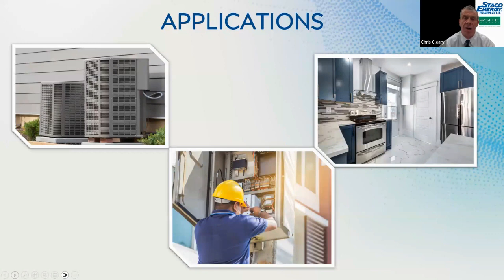We also have customers who are involved with UL 508 panels, where they're going to have to test the various different circuits that are within there. Is there some type of a circuit breaker? What does the circuit breaker do? You subject it to, say, 15 volts and 3,000 amps, and see what the circuit breaker would do in terms of its performance, so that you can be confident when it's moved into the field and put into a UL 508 panel.